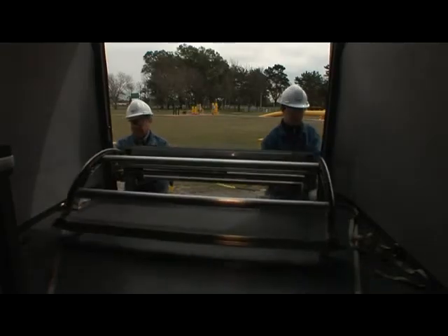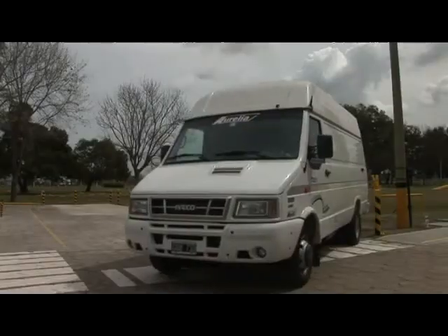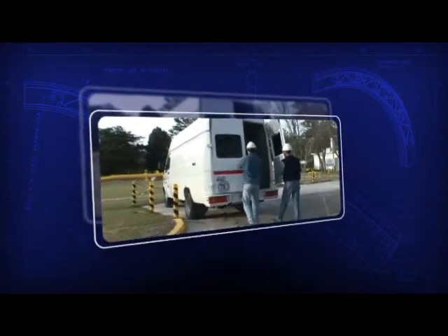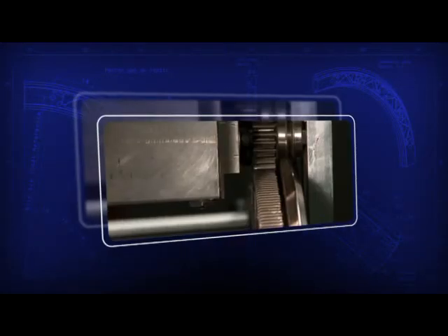The construction of the volumetric scanner for external corrosion measuring in pipes under operation allowed TGS to significantly reduce the time required for the defect evaluation work, with a precision 10 times greater than that obtained manually and a very low probability of human error.